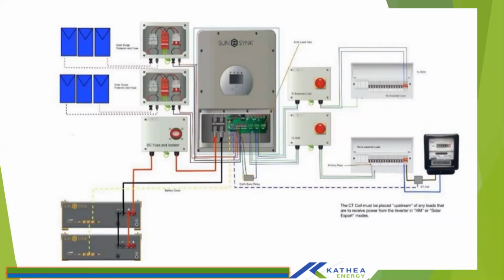So when you're installing a battery, I'm sure under electrical regulations, if you're an installer, you know that you always need a battery disconnector. It's recommended to install a protection box for the battery disconnector, basically a fuse, or you can even use an isolator on the positive terminal, such that you'll be able to cut out power coming from the battery to the inverter.